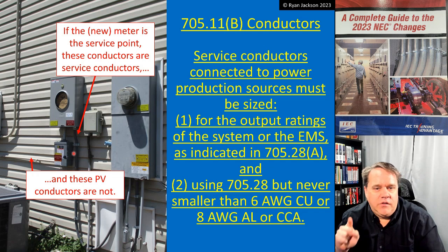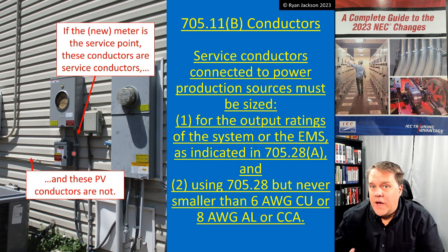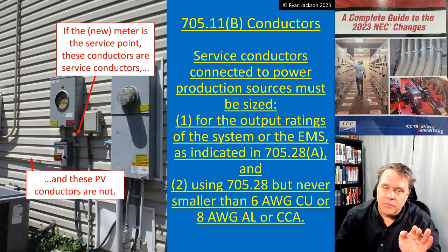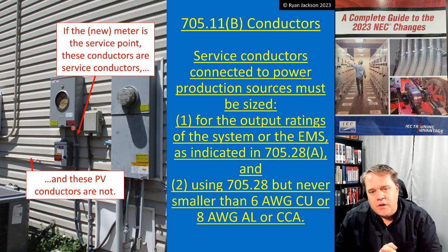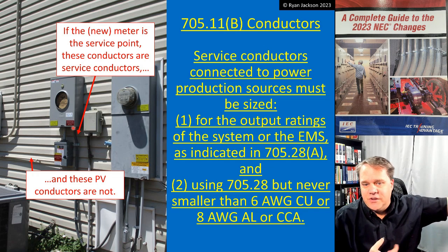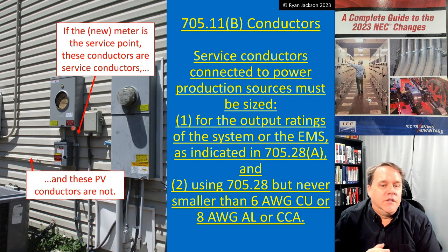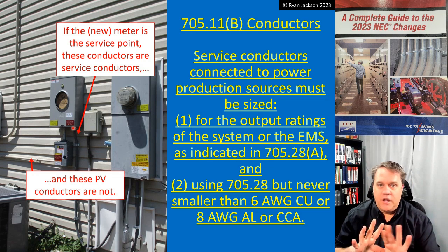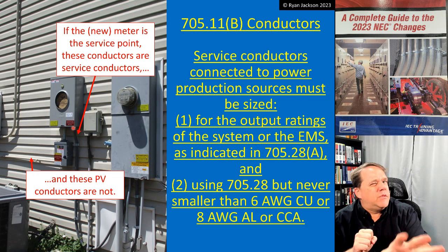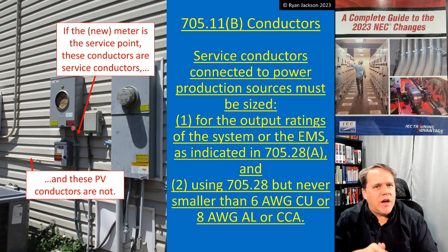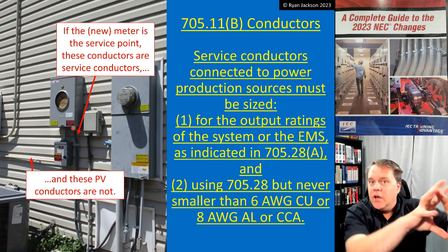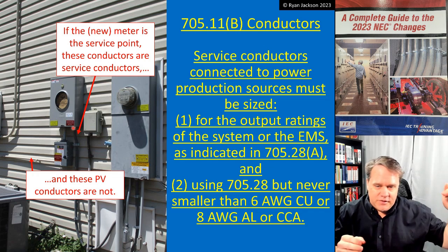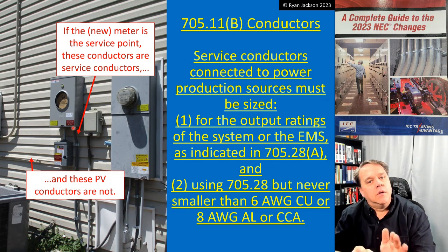How do you size service conductors? Service conductors do have minimum sizing requirements. Service conductors connected to power production sources — coming out of the PV disconnect to the meter — have to be sized for the output ratings of the PV system, or the power production system, or the energy management system as indicated in 705.28. So there are two ways to size those service conductors. Let's keep the discussion in the realm of solar to make it easy. You're going to size those conductors based on the capacity of your generating system — your PV modules — to carry the capacity of the PV system or the energy management system.